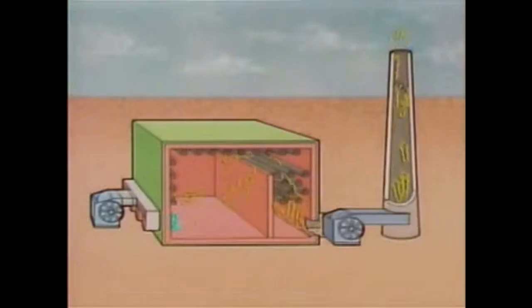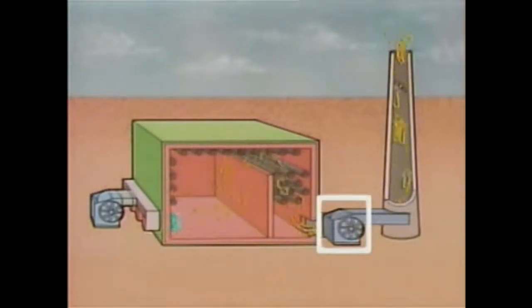Another type of furnace is a balanced draft furnace. A balanced draft furnace is similar to a forced draft furnace, but it has another fan in addition to the forced draft fan. The second fan is called an induced draft fan.